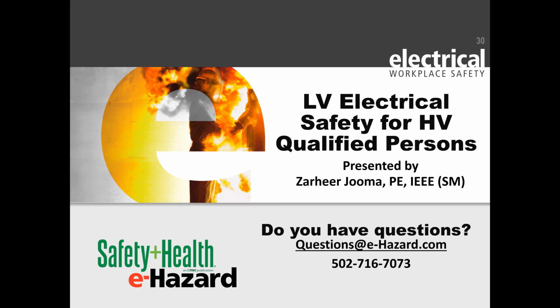Fortunately it didn't end very badly, but it was quite a disaster. So my recommendation would be rubber insulating gloves with overprotectors. You can use leather overprotectors, and these days there are other overprotectors that offer better cut resistance that can be used with rubber insulating gloves. Folks, at minimum, a class 00 electrical glove should be used.